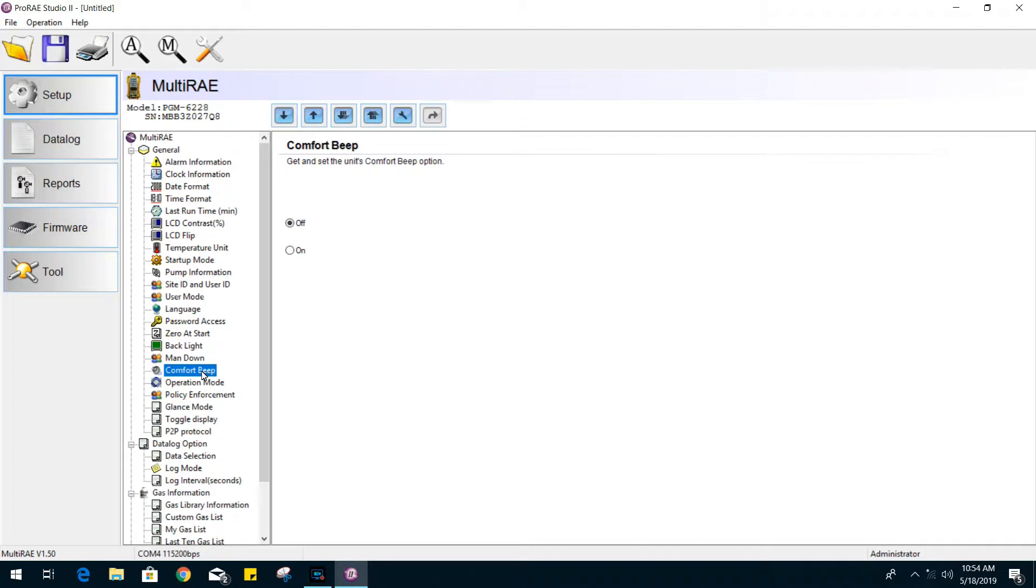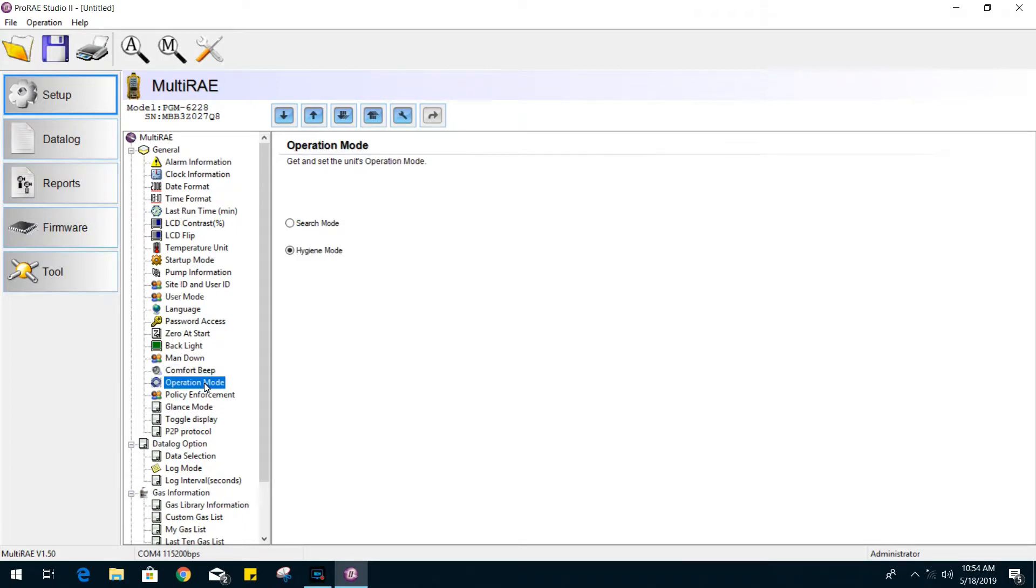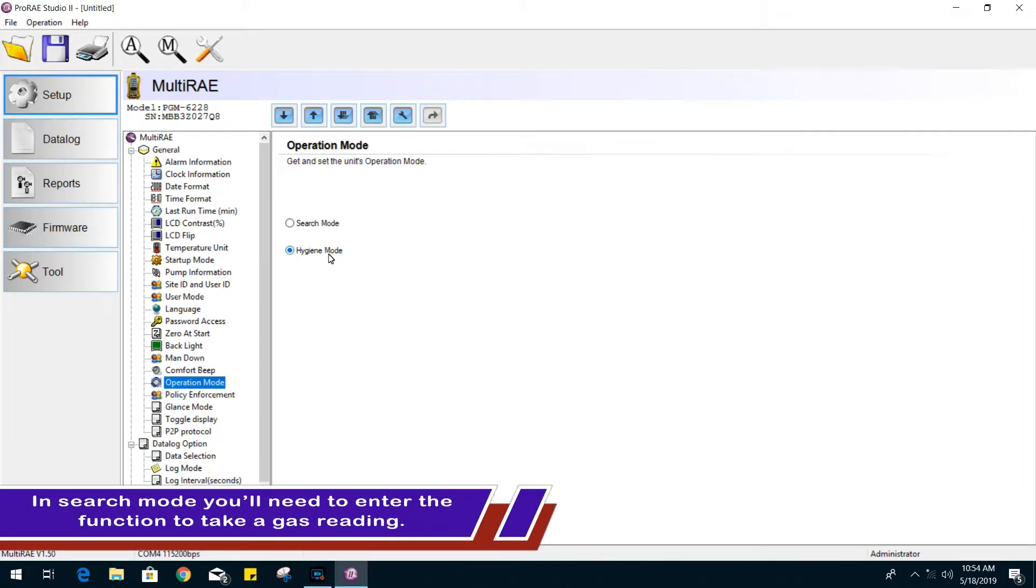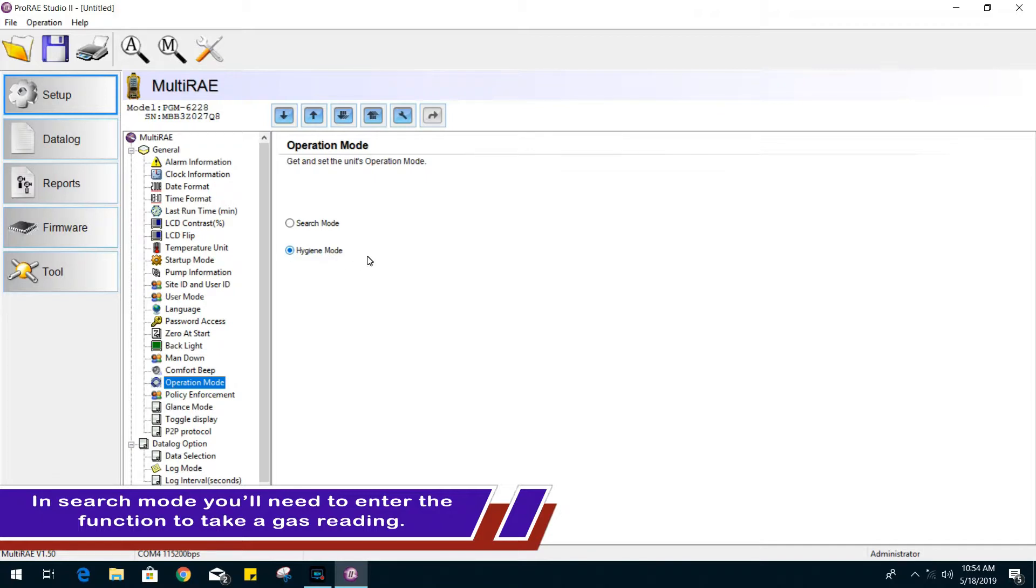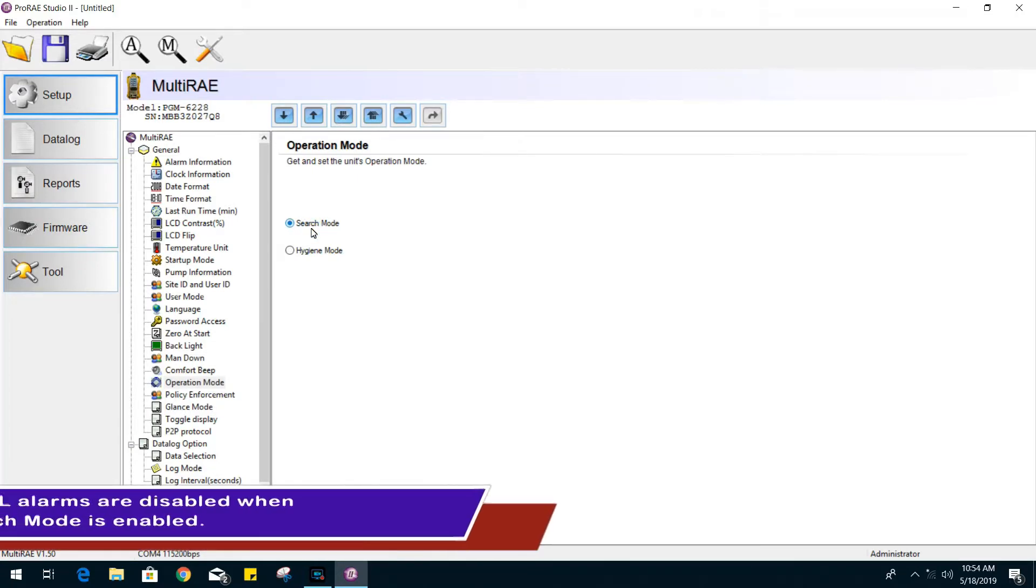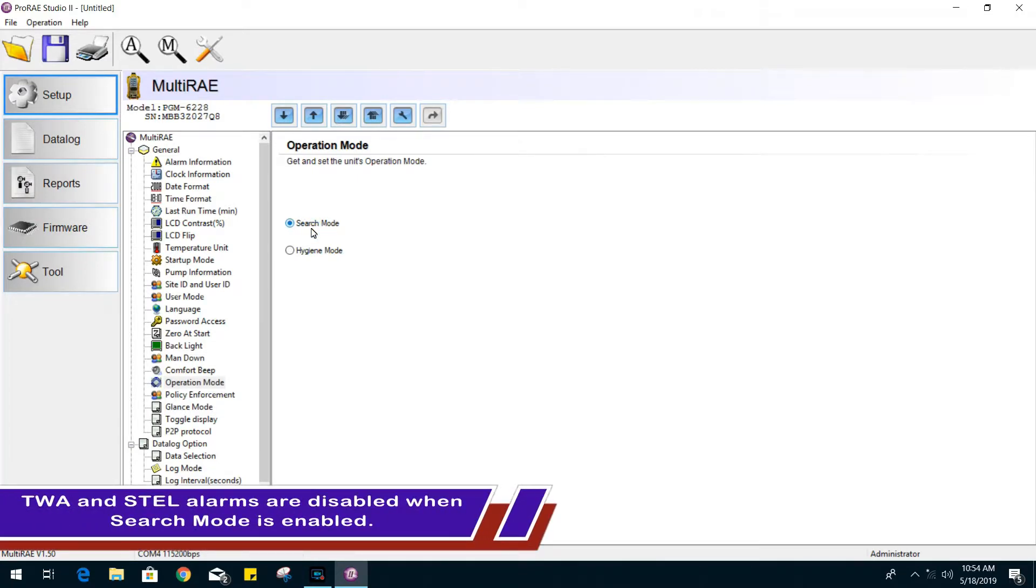Comfort beep will give off an audible indicator that the gas monitor is operational. In operation mode, you have either search mode or hygiene mode enabled. By default, you will have hygiene mode enabled and it will start to give a live reading when powered up. In search mode, you will have to enter that specific mode in order to get a sample gas reading.